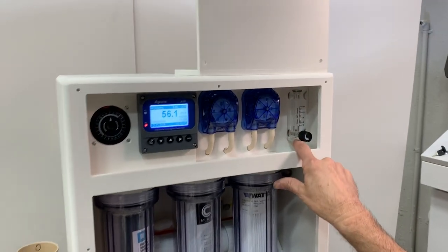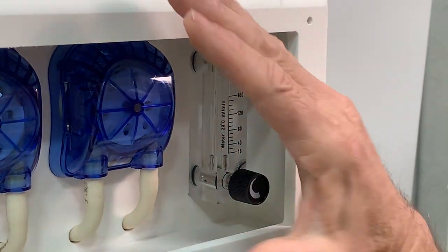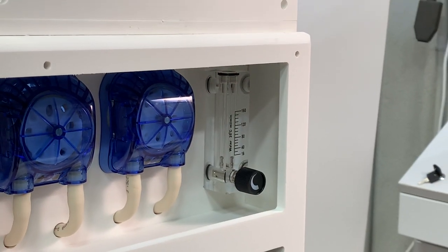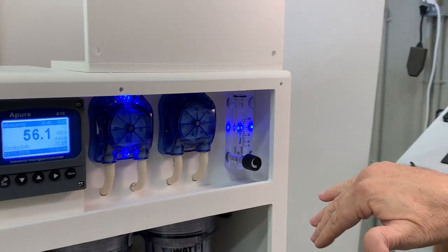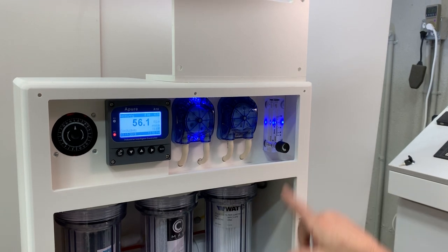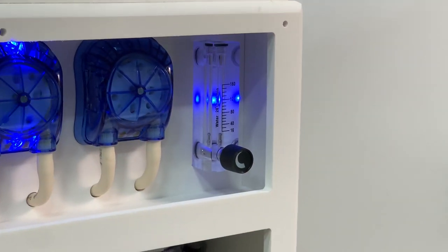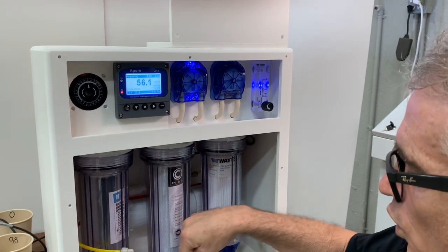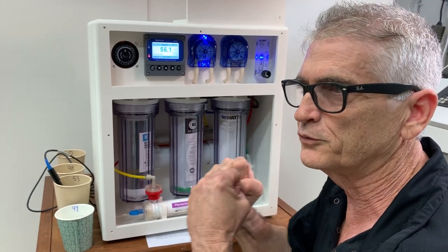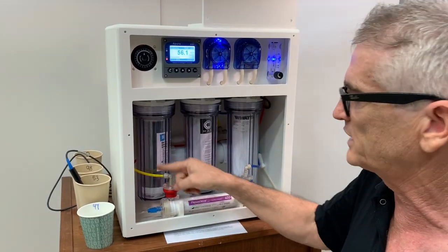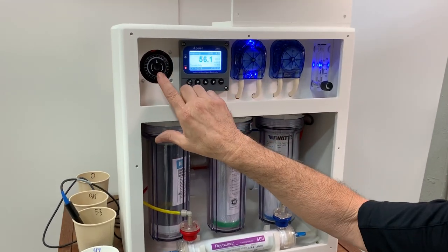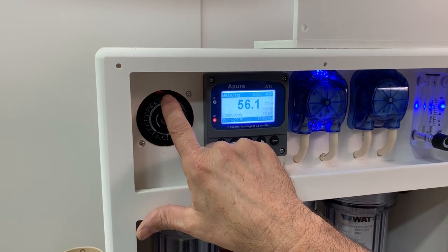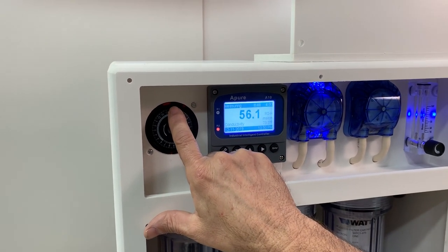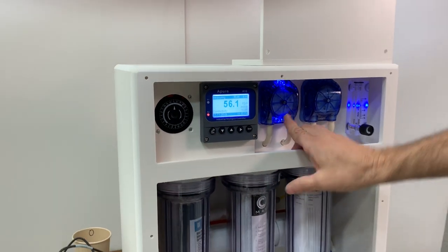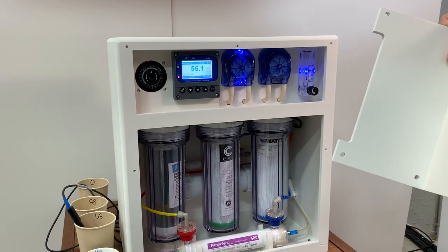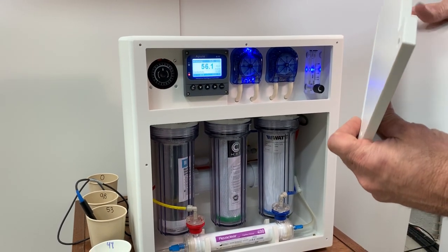There's a flow meter here, because sometimes, depending on where you mount this machine, if it's below your sump, or above your sump, or a far distance away, we need to put a head pressure. By turning this knob to the right, we're putting a head pressure on the water that's going through the dialyzer, so it actually forces more salt water to leave, going down the drain. Now, as I was talking to you, the timer got to the first time of the day that we had set the controller, and it's actually changing water. And remember, I said it's changing water at a rate of 0.4 gallons for every segment, or 1.4 gallons every hour.